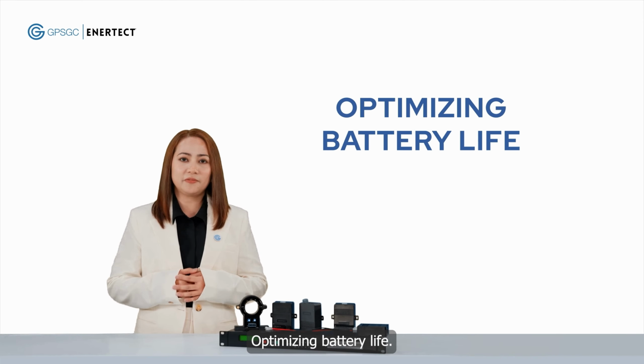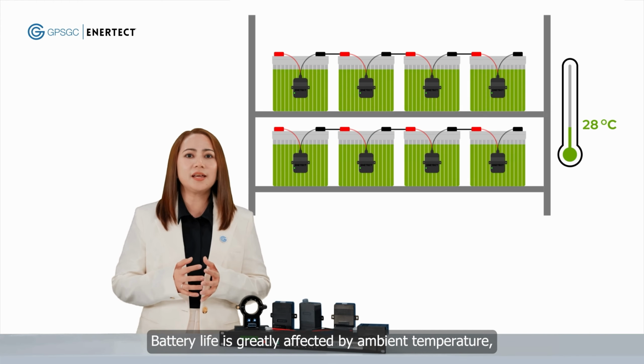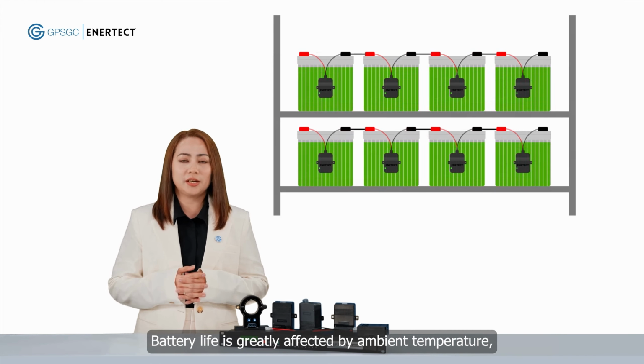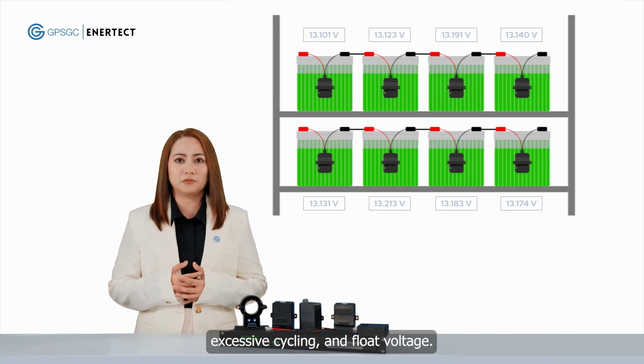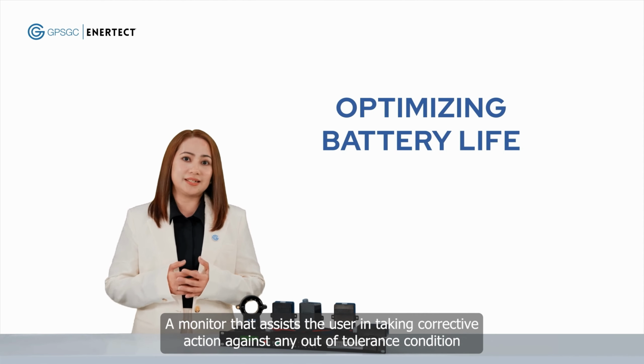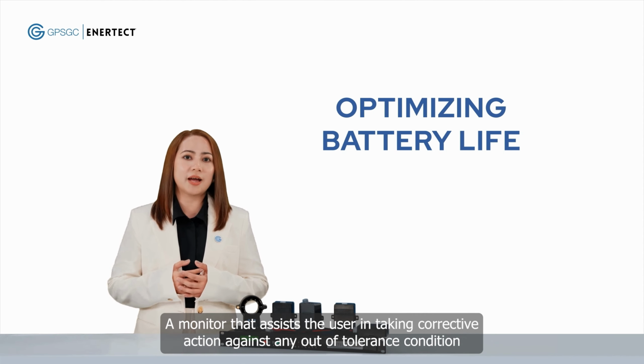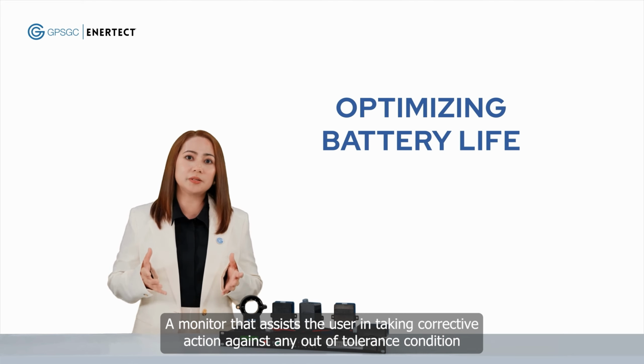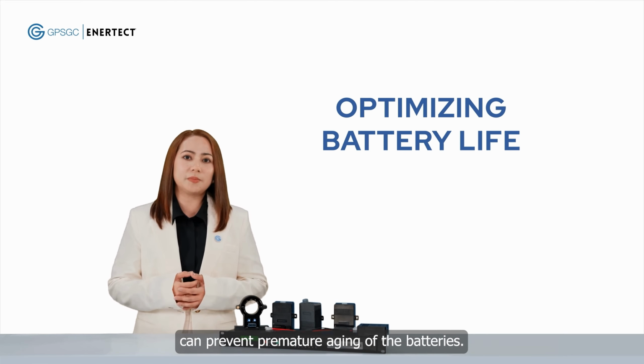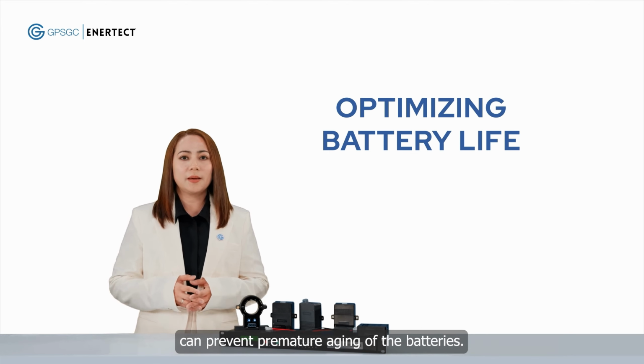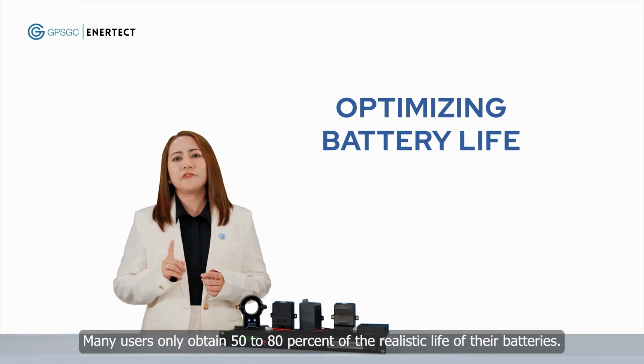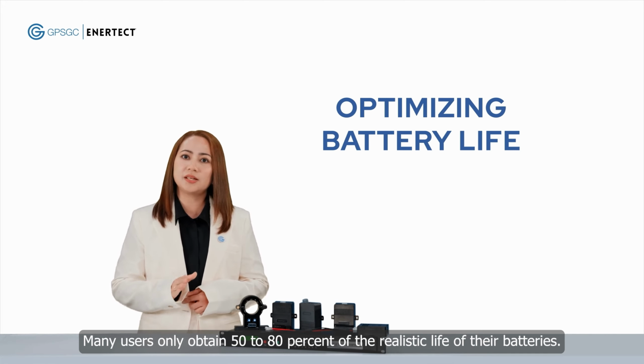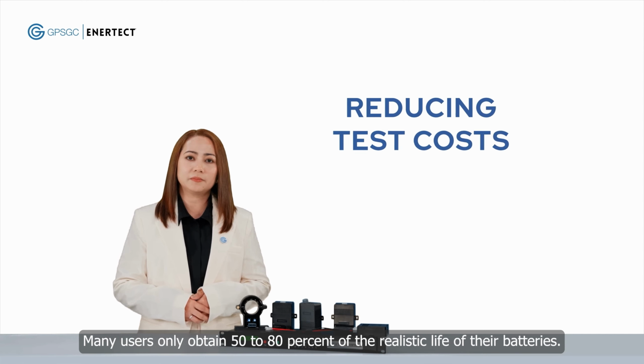Optimizing battery life. Battery life is greatly affected by the ambient temperature, excessive cycling, and float voltage. A monitor that assists the user in taking corrective action against any out-of-tolerance condition can prevent premature aging of the batteries. Many users only obtain 50 to 80% of the realistic life of their batteries.